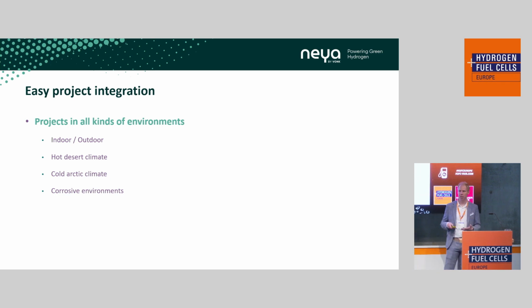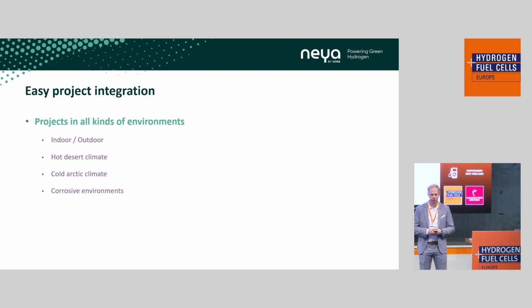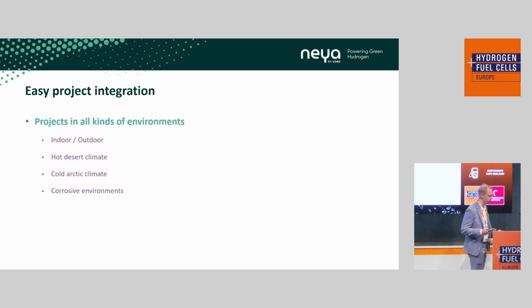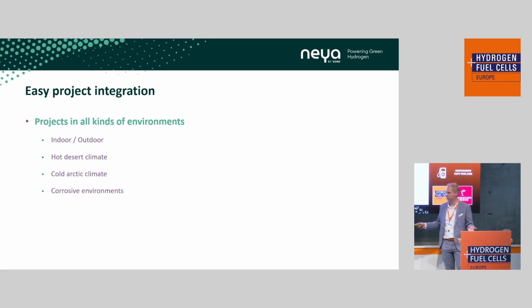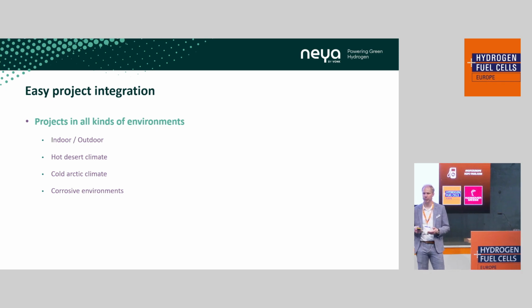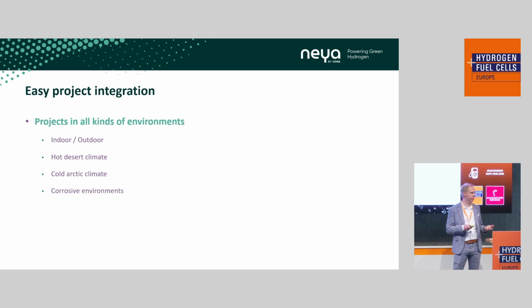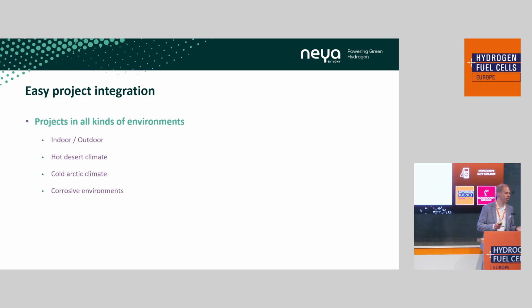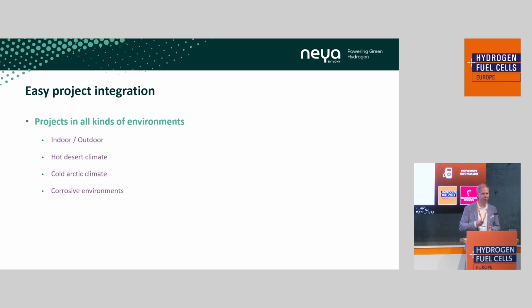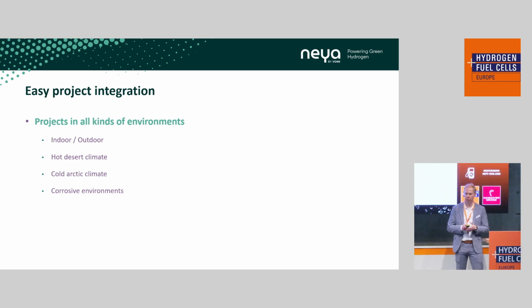Where and how you apply your project matters. Indoor and outdoor placement really makes a difference. If you're placing indoors, you can work with skids and so on. If you work outdoors, you have to work with your environment. If you're in an environment with a lot of corrosion, for instance at a chemical site or near the coast, you need different protection measures than inland with, say, a steel factory. And there's quite a difference between working in an Arctic climate like Scandinavia versus a desert climate in the Middle East. All these things have to be taken into account when integrating your rectifiers.